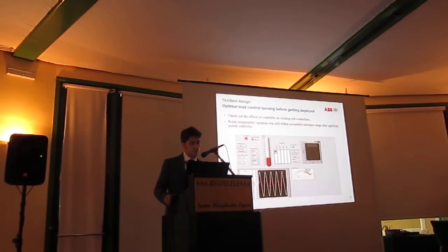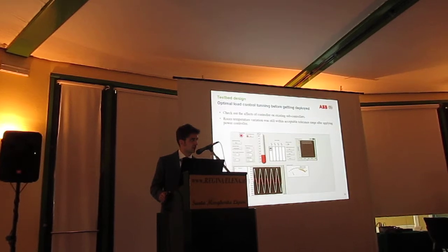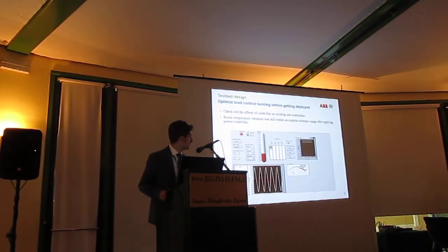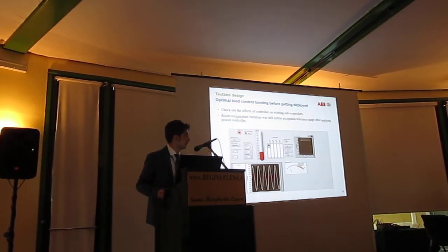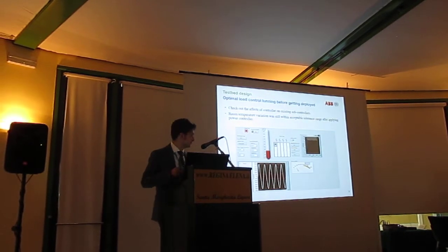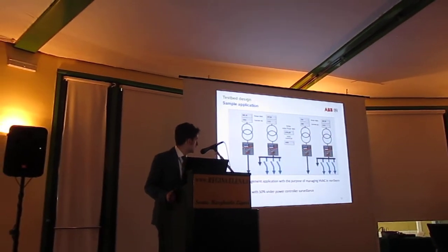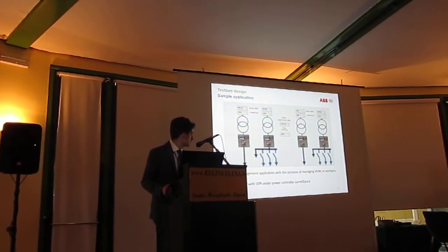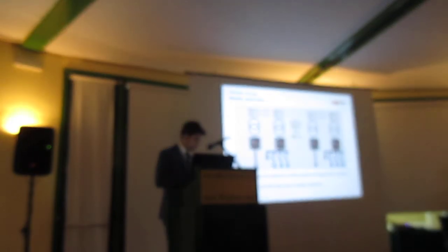So we have placed our cooling system, our heater, under the power controller, and we saw results which show that the controller didn't affect the final operation negatively. Here is also another real study case on HVAC loads in Northern Europe, half of which were under the supervision of the controller. 4 megawatts was the total load, half of which, as I said, were under the supervision.